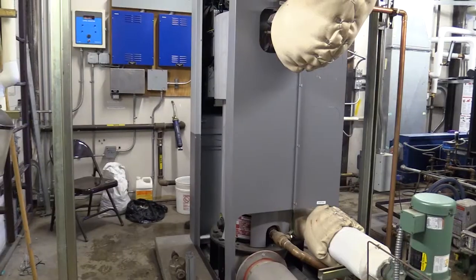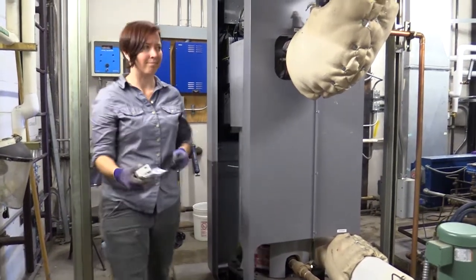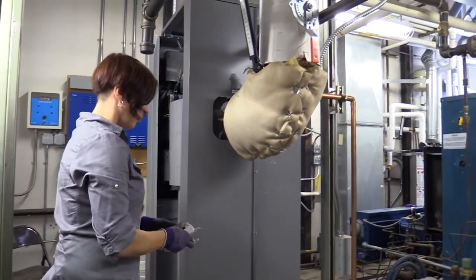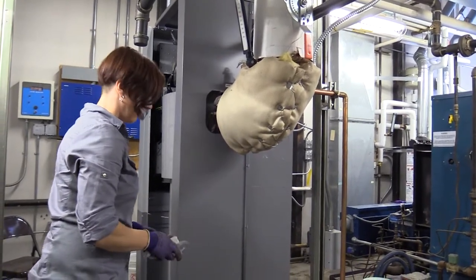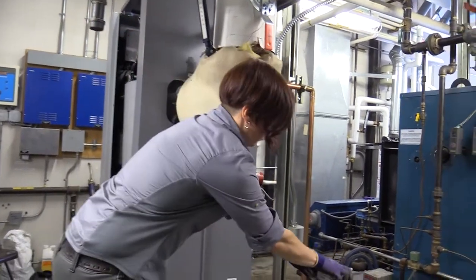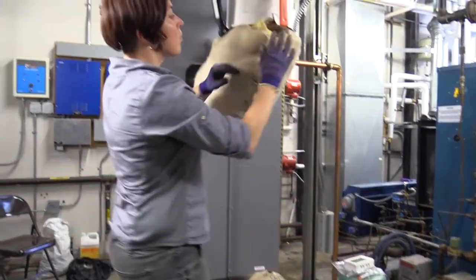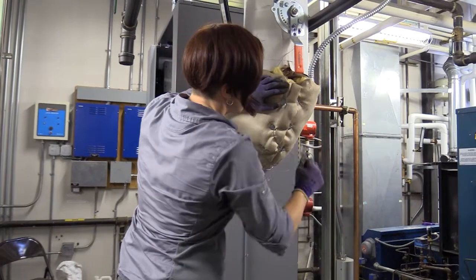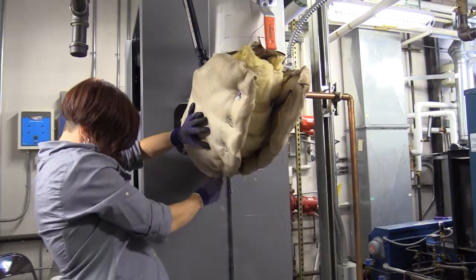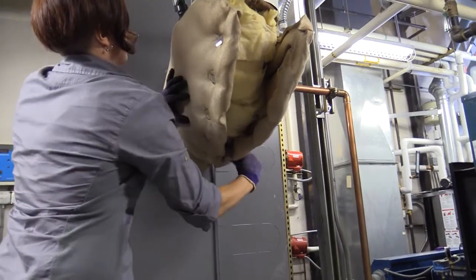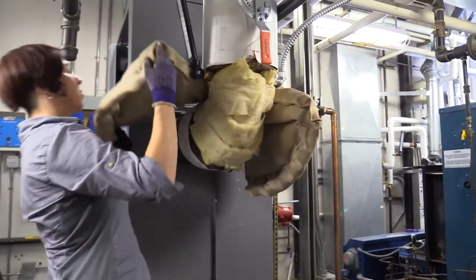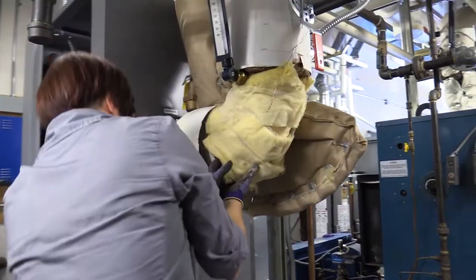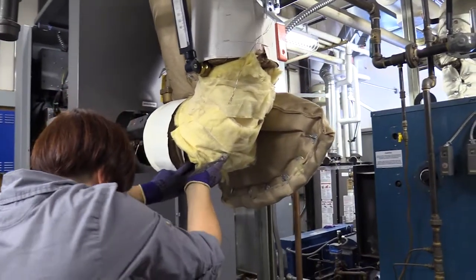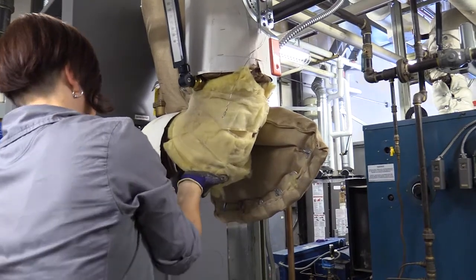Now that we've configured both loggers, we can head to the boiler room where we can capture some data. In the boiler room, you'll first want to identify the supply pipe coming off of the boiler. You'll want to place the temperature sensor in a section of insulated pipe at least 12 to 18 inches in length. This is to ensure that you're measuring the pipe temperature and that it's not affected by ambient influences. When removing your insulation, make sure to do so carefully so that you can replace it in good condition easily.